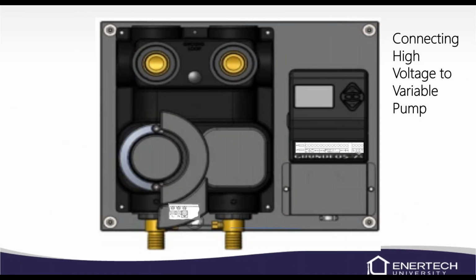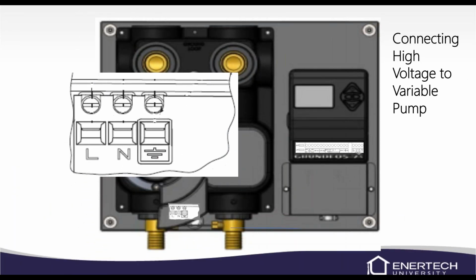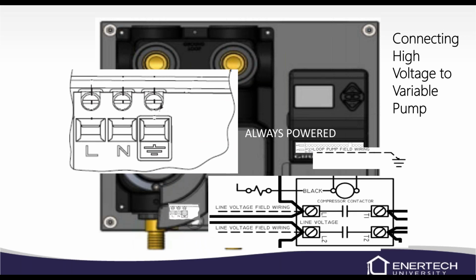High voltage: the variable speed pump needs high voltage all the time. So it's going to come off your contactor on the inlet, your L1 and L2 on your contactor. If you've got an ECM blower motor in a packaged unit, that's where the ECM blower motor wires in as well, to the L1 and L2 side of the contactor. So it has power all the time, and the pump will come on using the low voltage signal.